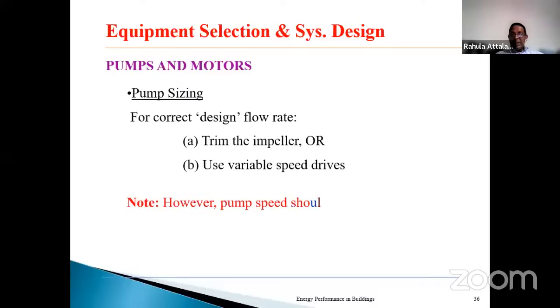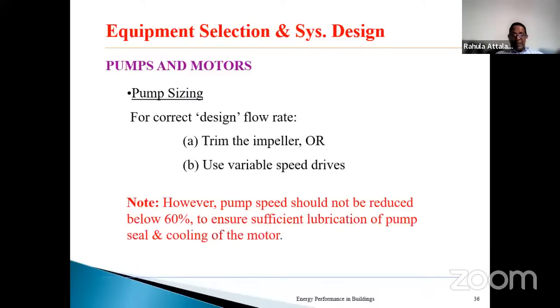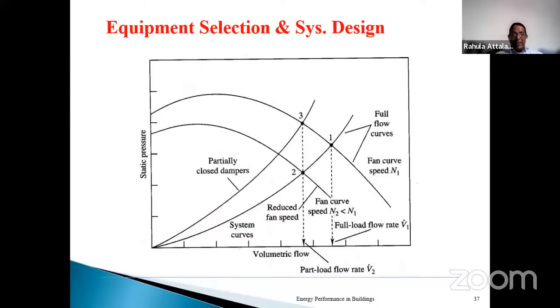Variable speed drive is an expensive element. For example, if you want to reduce the flow rate from 1 to 2, one will operate at one particular speed N1, and 1 to 2 can be changed by closing the valve and operating on the same curve and going to 3. But what you can also do is change the speed of the pump to another speed N2, which is less than N1, and then automatically, on the same flow conditions, your flow rate will be reduced.